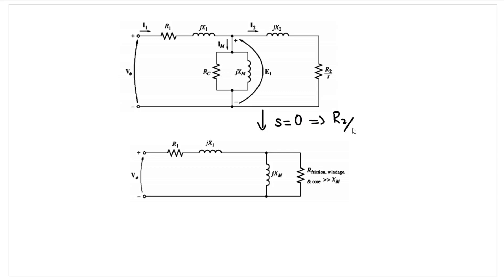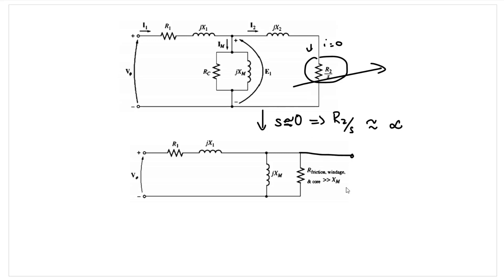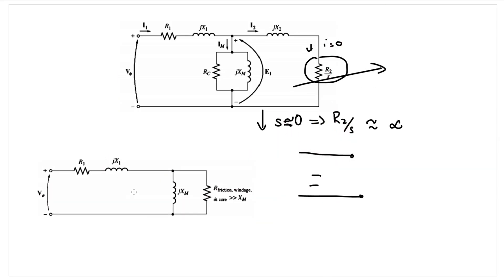Since slip is approximately 0, r2/s is approximately infinity, so an infinite resistance is offered by that path — no current flows through it, meaning an open circuit. We also combine the resistances rc, r_friction, and r_windage into one resistance. Our equivalent circuit then reduces and can be used to calculate the parameters r1, x1, and xm.